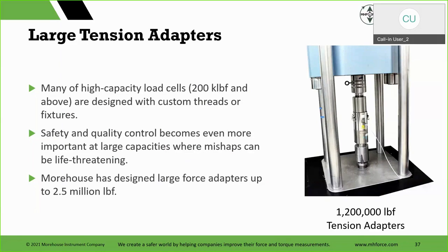At Morehouse, we design things with at least a 2-to-1 safety factor. If you're in the lifting business, it's 4-to-1. We try to over-design some things. It just depends. It's a conversation with the customer on how big you want to go. On that adapter, we've seen old BLH type cells with 8-inch threads to 1 million pounds. Is that needed? No. It was super safe, but is it needed? Going to 1 million pounds today, you can go 4.5 or 5-inch. We prefer to go 5-inch because it gives you more safety, but some manufacturers out there are pushing the limits and really trying to eke out that 2-to-1.